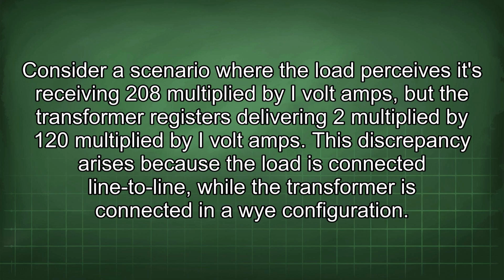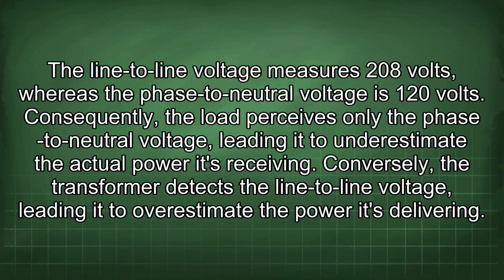This discrepancy arises because the load is connected line to line, while the transformer is connected in a Y configuration. The line-to-line voltage measures 208 volts, whereas the phase-to-neutral voltage is 120 volts. Consequently, the load perceives only the phase-to-neutral voltage, leading it to underestimate the actual power it's receiving. Conversely, the transformer detects the line-to-line voltage, leading it to overestimate the power it's delivering.